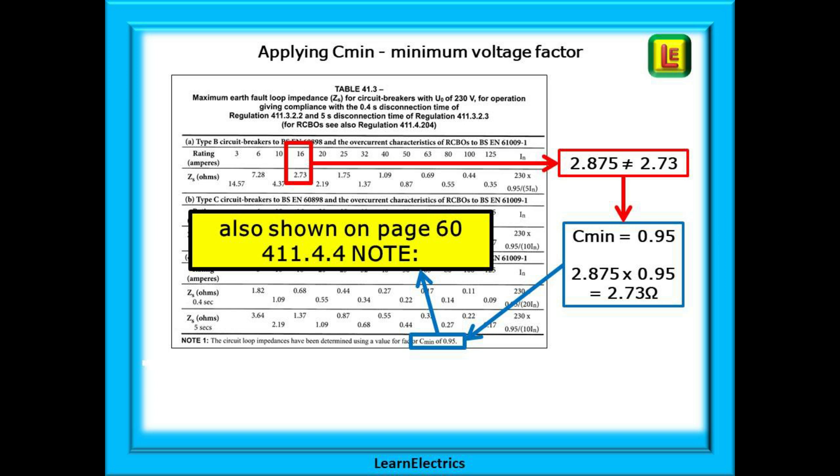We must multiply 2.875 by 0.95 and out pops the answer 2.73 which now matches the table. So all the ZS values shown in the tables have had a C min of 0.95 applied to them.